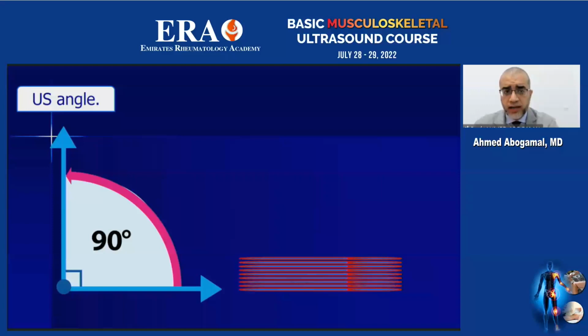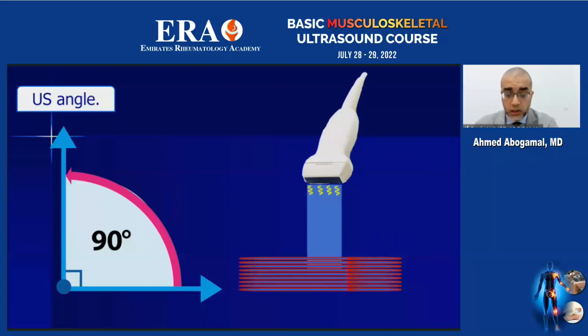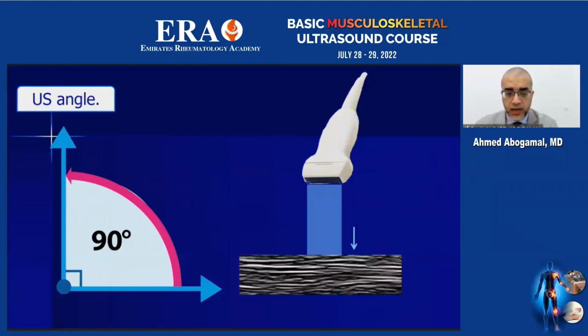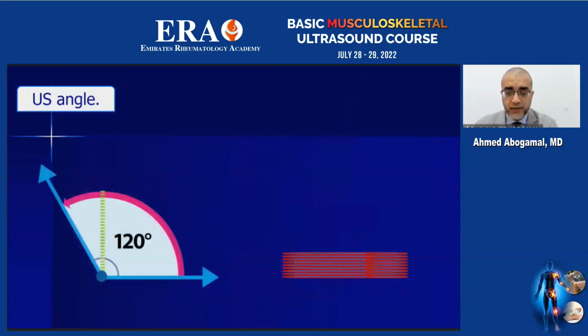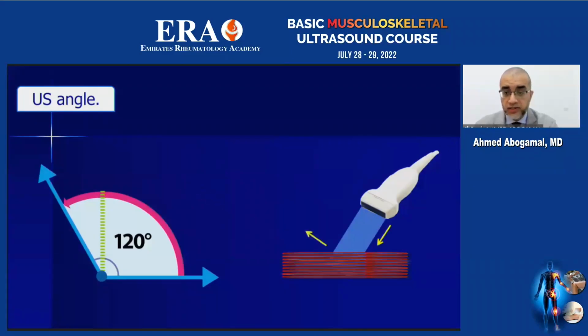And we have what is called the insonation angle, which is the relation between the footplate of the probe and the long axis of the examined structure, and usually we try to keep these two lines as parallel as possible between the footplate and the long axis. So the ultrasound waves cross the long axis of the examined structure at a 90-degree angle, which makes sure that most of the ultrasound waves are reflected back to the ultrasound footplate and gives a good quality image without any artifact called anisotropy, as we are seeing here with an oblique angle. Already we have the ultrasound wave reflected back away from the ultrasound probe, so it's not received, which gives us a black image, and we call it anisotropy.